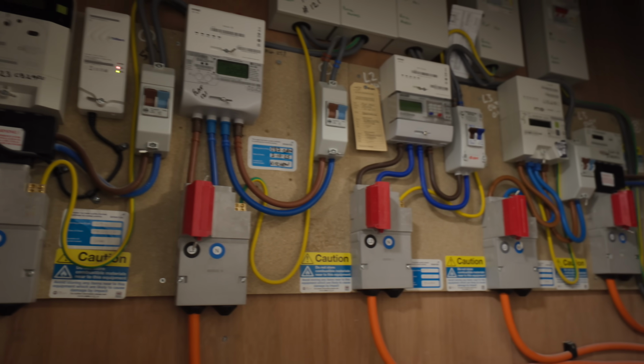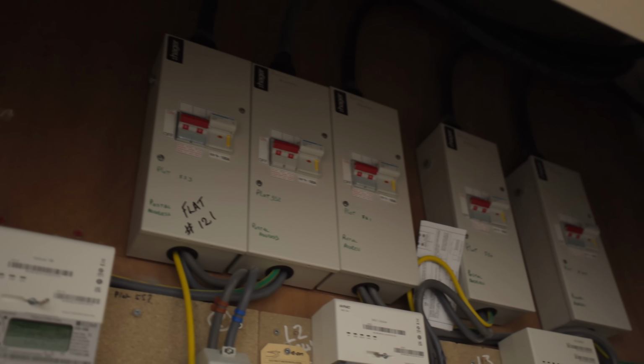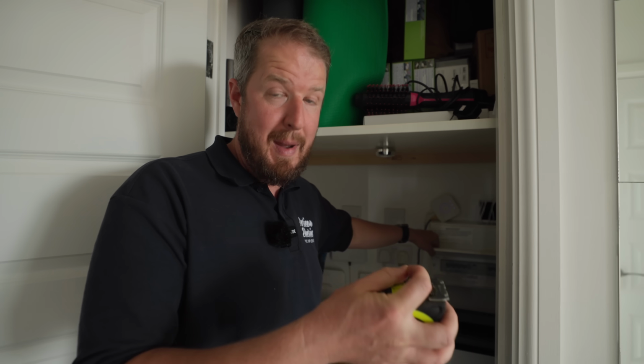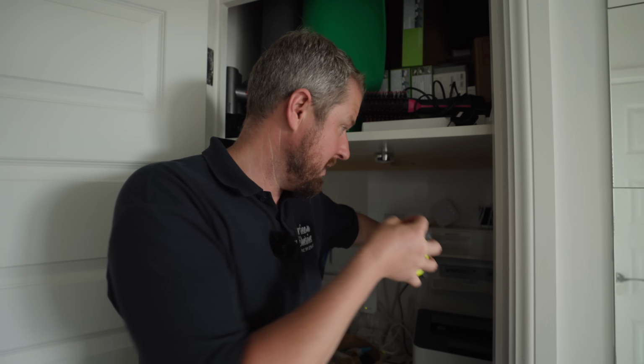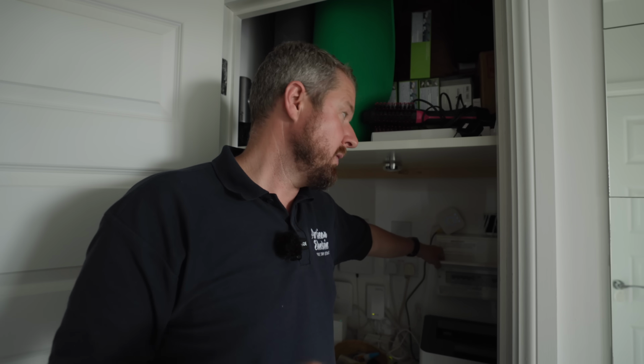There's no socket to plug it into or anything like that, which means the only way to fit a CT clamp in this setup would be to take the lid off the consumer unit and clamp around the main tail that goes into the main switch within the consumer unit. But obviously that's not a DIY job. Homeowners should not just be taking the cover off their consumer units because there are live parts that could be exposed that could be potentially dangerous. So you will need to get an electrician to install that meter, even if the rest of it is a so-called DIY job.